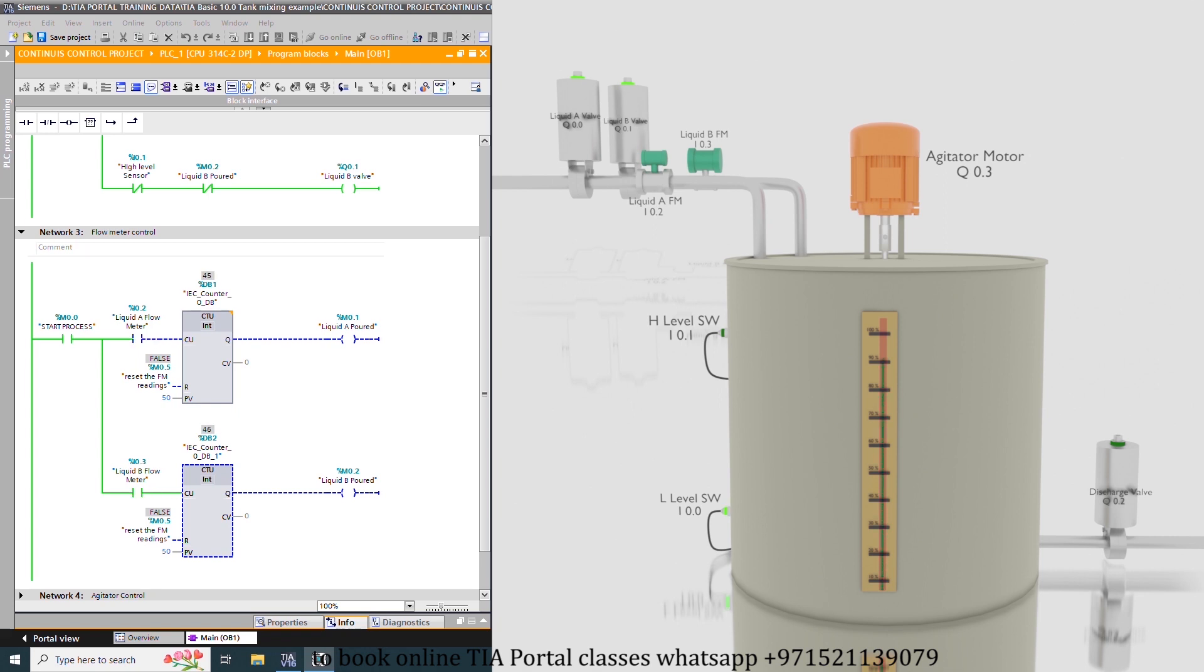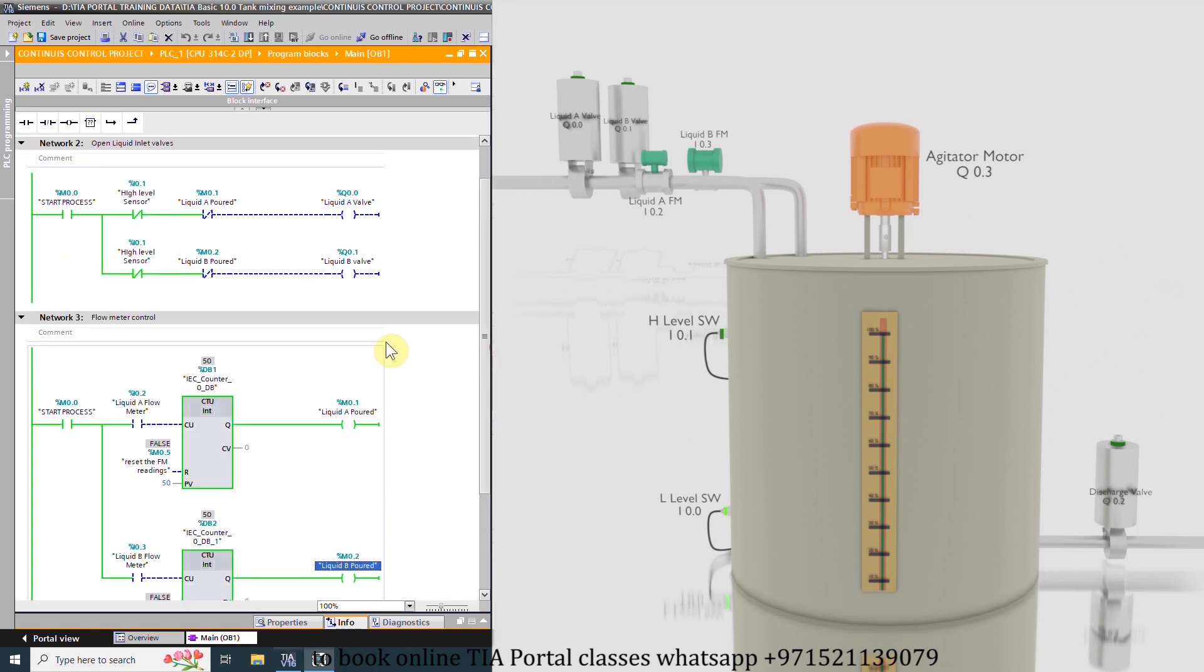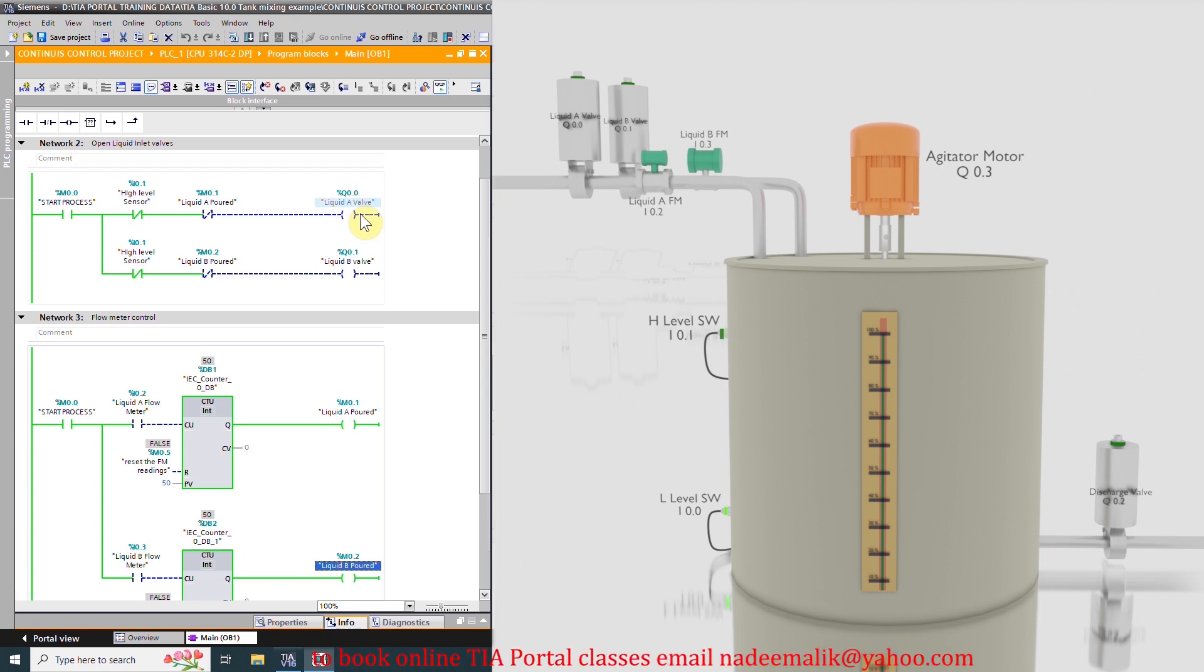Once the 50 liters of the liquid from both flow meters is measured by these counters, it will turn on the bits M0.1 and M0.2. And these bits have turned off the liquid A and liquid B valves outputs of the PLC Q0.0 and Q0.1.